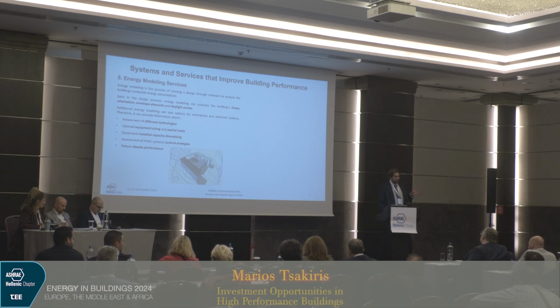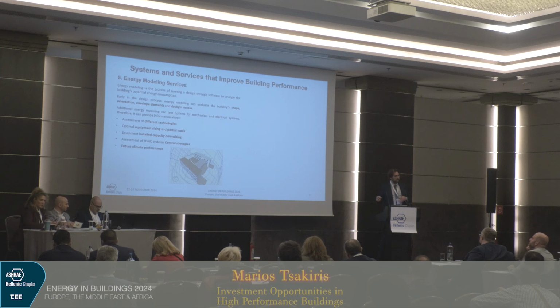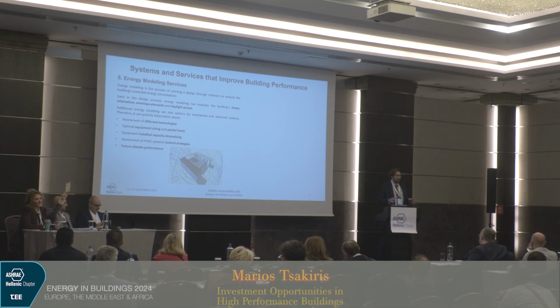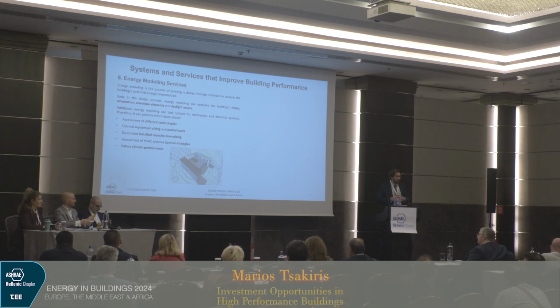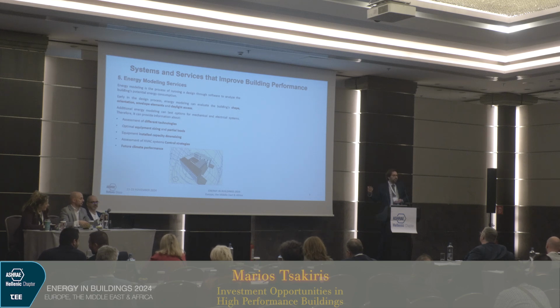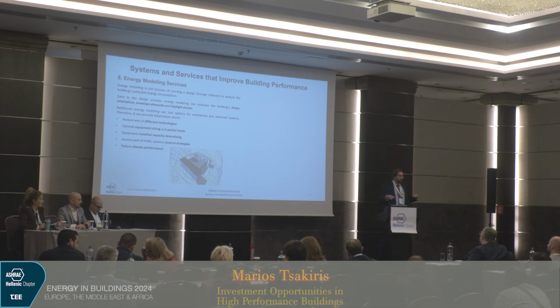When we size the system, most of the time we size it for the worst conditions, climate and occupancy, for the whole building. In a large building, 10,000, 30,000, 200,000 square meters, there is no case where the whole building needs cooling at its peak or heating at its peak at the same time. So you find that peak loads are only at part of the building, while another part might need heating instead of cooling. There are many cases where modeling can create capex reductions.